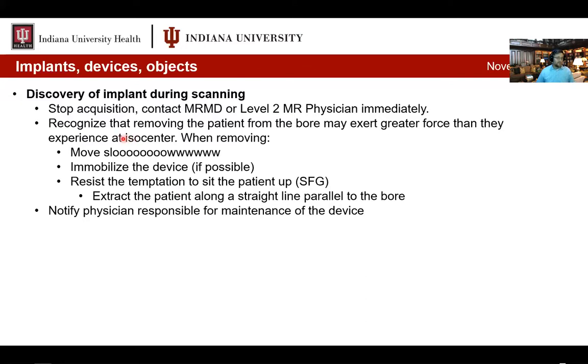Move slowly though, because you can reduce the torque experienced by the device. Also resist the temptation to have the patient sit up as soon as they get out of the bore. The correct way is to move them as far out as you can, keeping them parallel to the bore. If your table can undock, actually undock it and bring them out of zone 4. The safest way is to keep them parallel to the field and bring them straight out in a straight line. Please try to do that as much as possible.